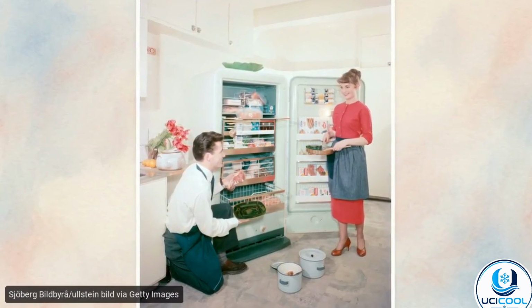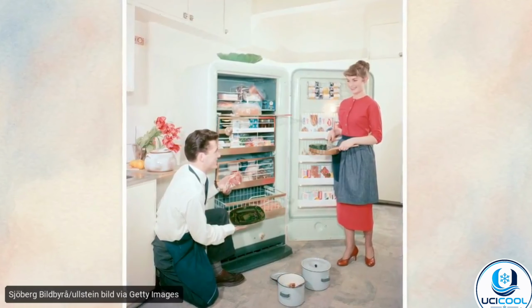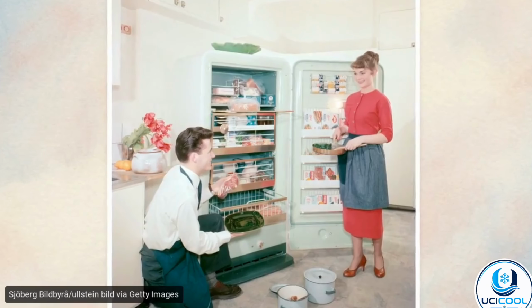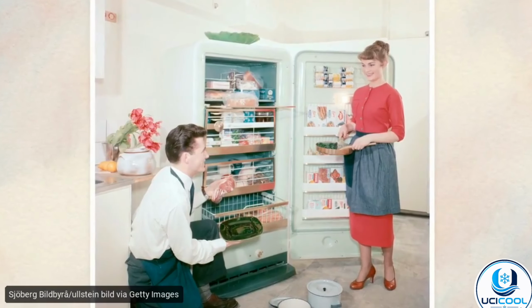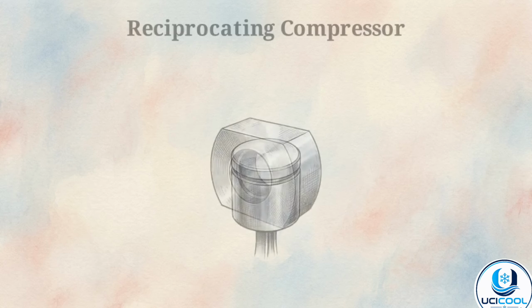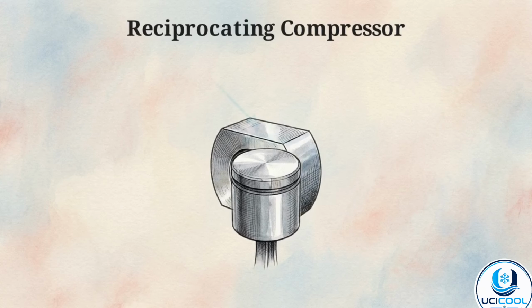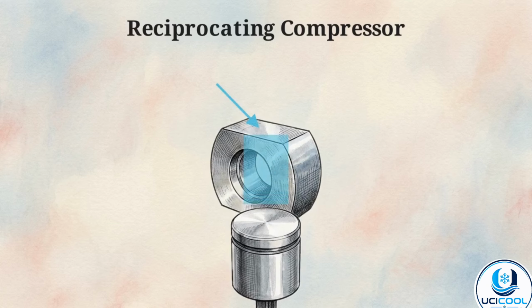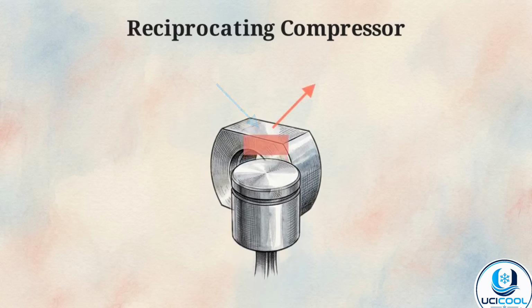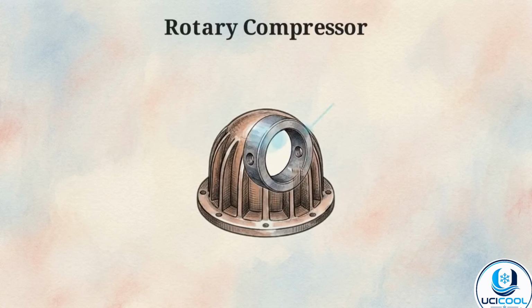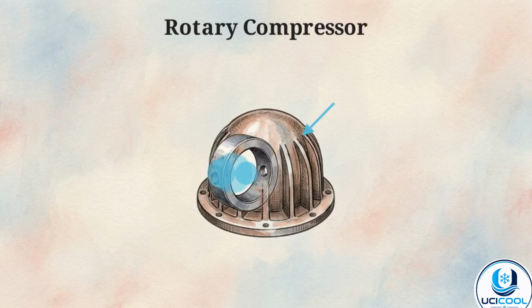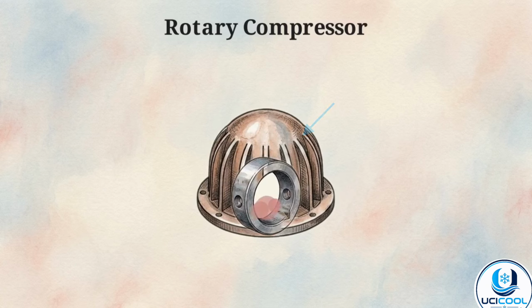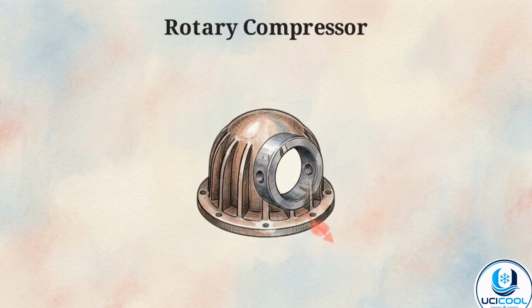In small-scale applications like a domestic refrigerator, the volume of heat to be moved is relatively low, allowing for simple mechanical designs. This is the reciprocating compressor. A piston moves inside a cylinder, pulling in refrigerant and crushing it into a high-pressure gas. Alternatively, small systems use a rotary compressor. A rotating roller pinches the refrigerant against the wall, achieving the same pressure with fewer parts.